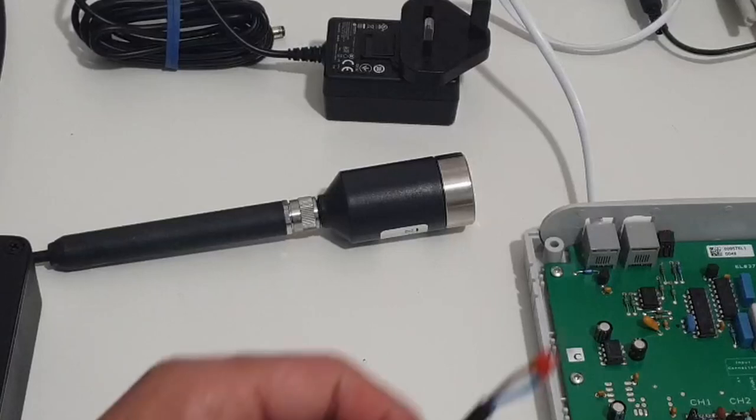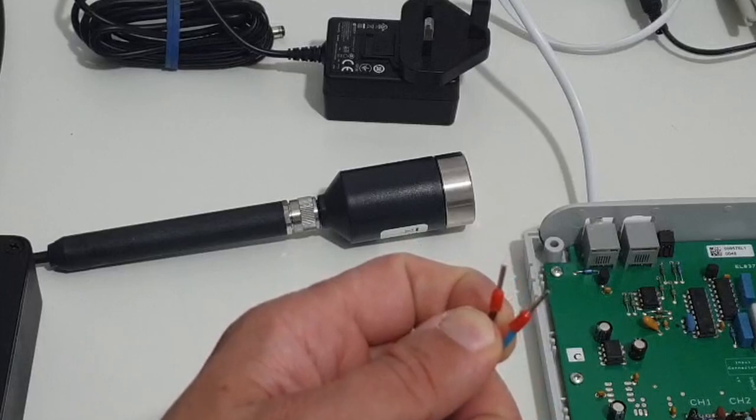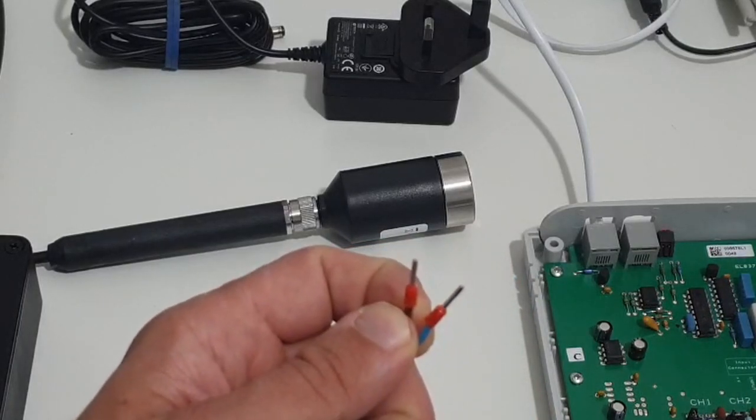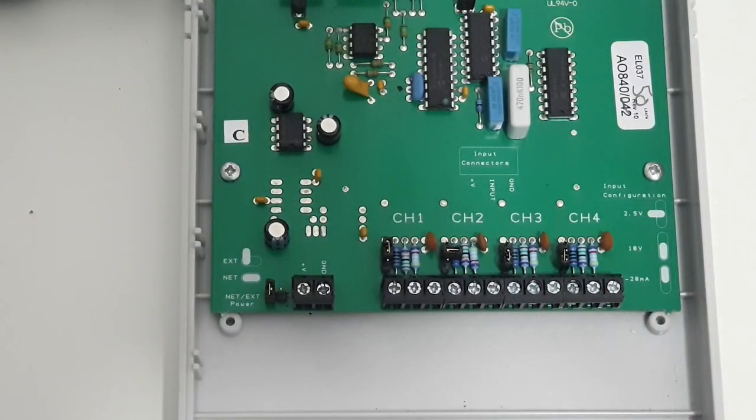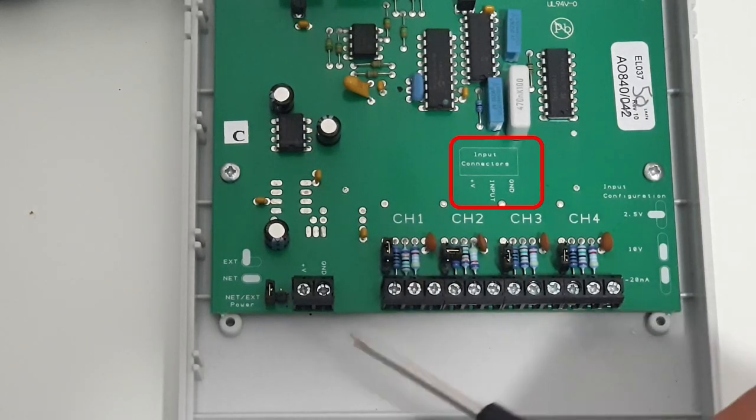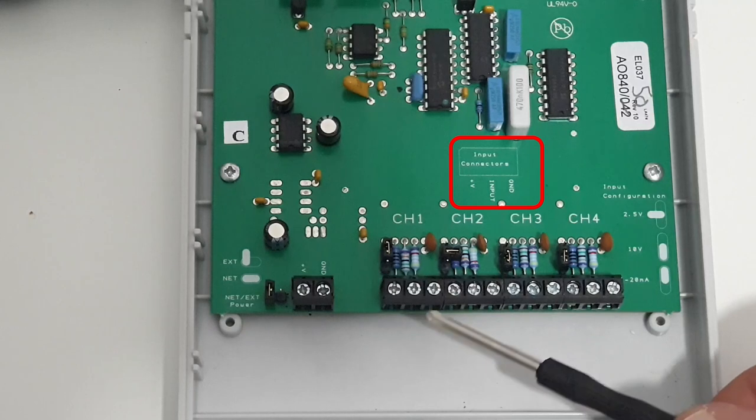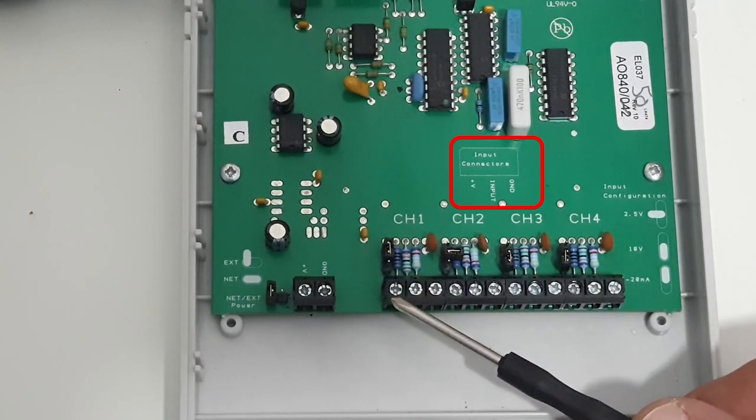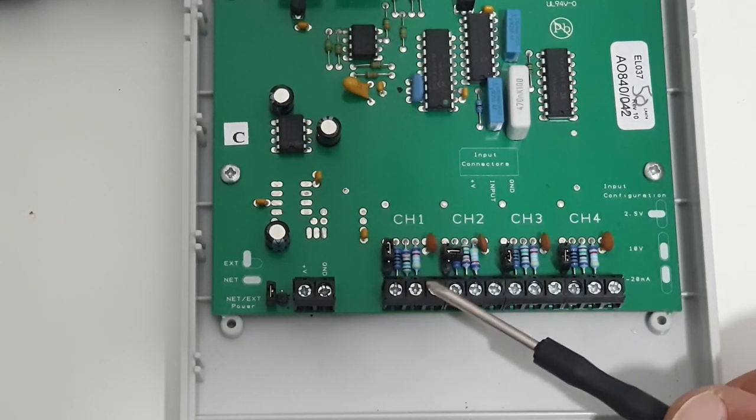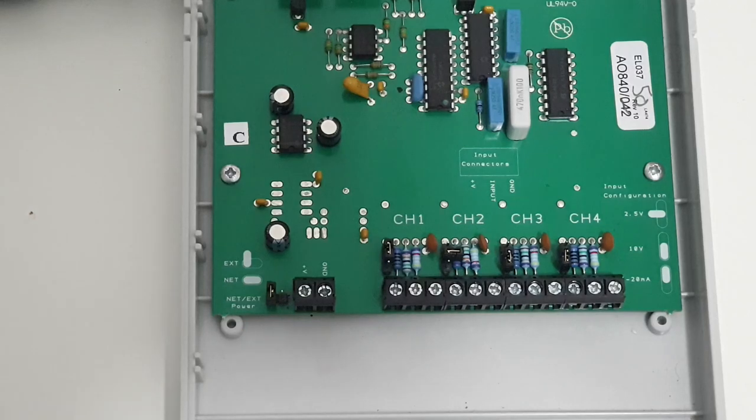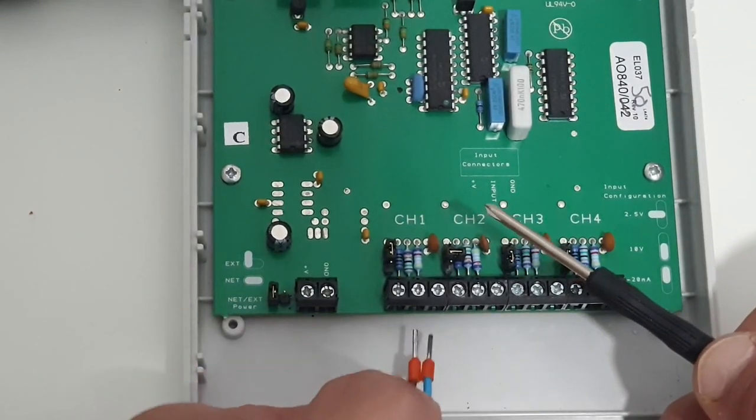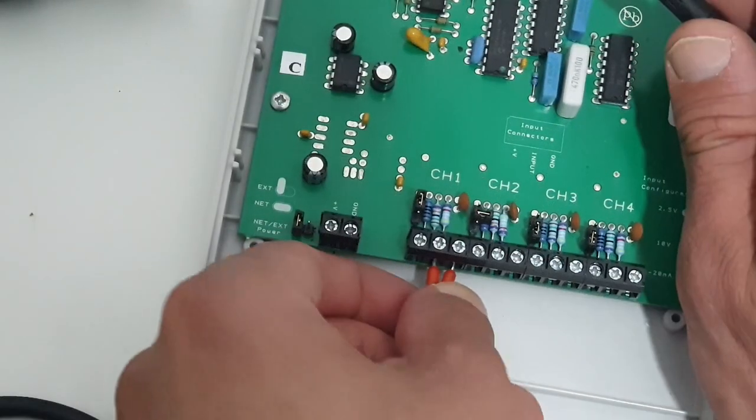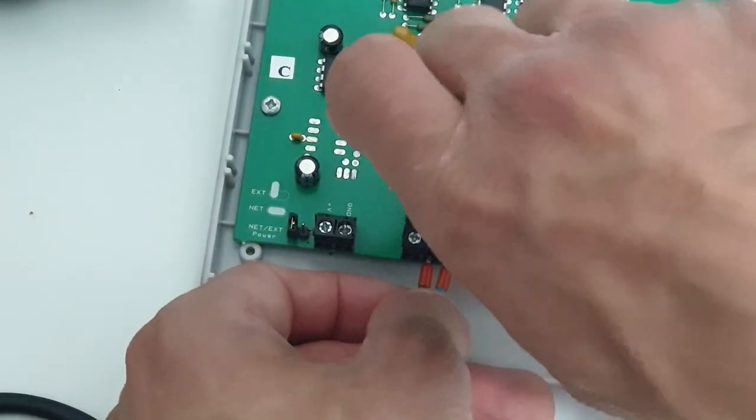So the wiring on this probe has two pins, where brown is the input signal and blue is the ground signal. So we can connect that to channel one. Now if we were to look at the terminal board, we can see a number of inputs. So each of the channels has three pins: ground, then the input signal, and then plus V, which is the source for the power if you wanted to power the sensors. But we're not using this today and we're only using the input and ground. So as I said, brown is the input signal and blue is ground in this case. So we'll feed those in like that and then do the screw terminal.